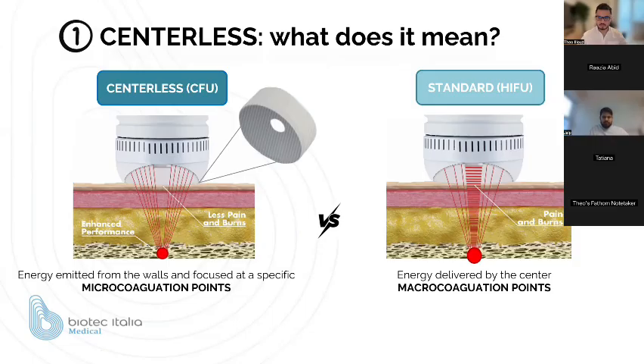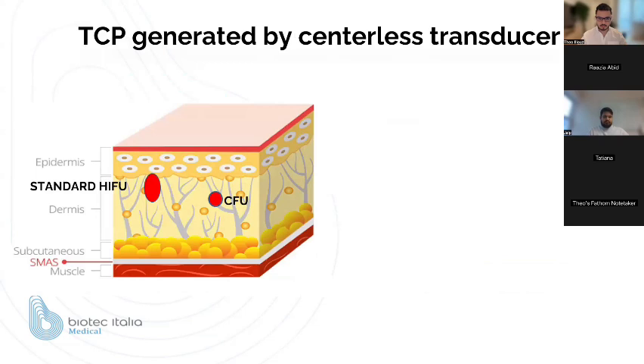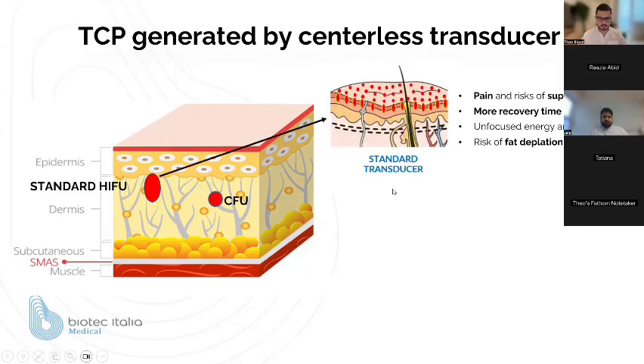As a result, we have microcoagulation points, very small points compared to the standard HIFU, which, due to the fact that it emits ultrasound directly from the center, has bigger thermal coagulation points. In these slides, you understand the difference better. This is the microcoagulation point of the CFU, and this is the shape of the macrocoagulation point generated by the standard HIFU. You can see that the point spreads a little and also interferes with other biological tissue.